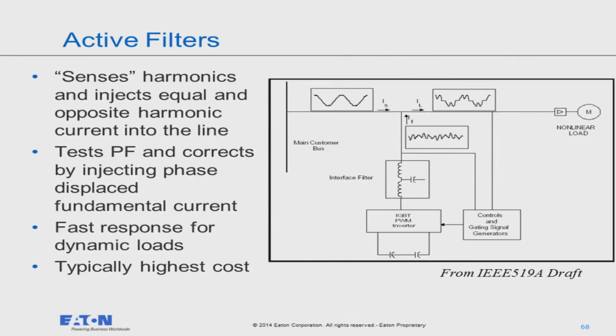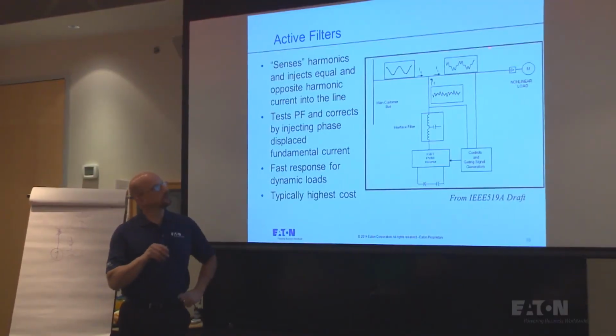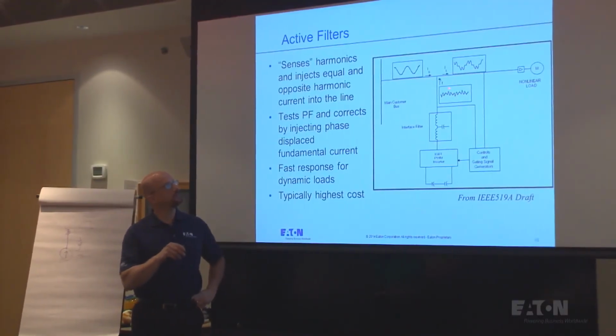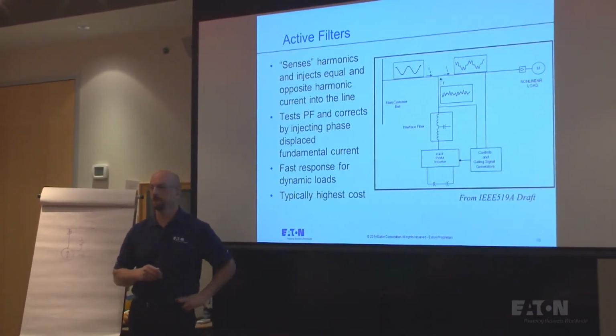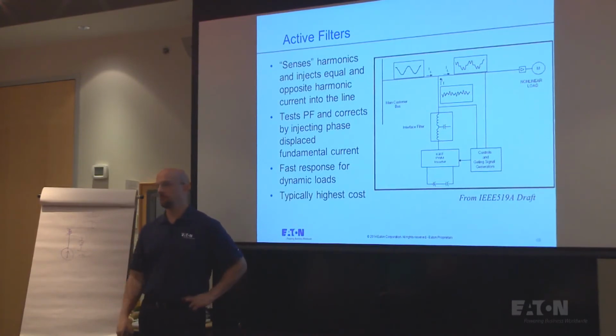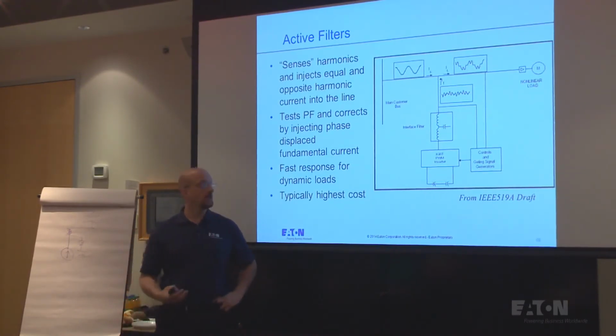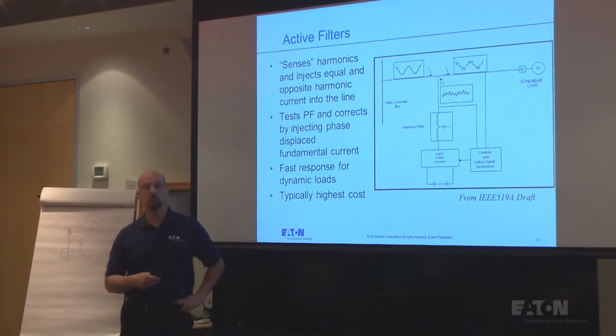Active filters. An active filter would be kind of a system level fix where you have a whole bunch of drives and you don't know what speed they're running and what kind of harmonic output they're generating. But then it'll match up and inject equal and opposite harmonics. So it sees a load that looks like this, it injects this, and these two added together look like that. Does it have to be perfect? No. It just needs to be better than it was, or better than the threshold of pain, so to speak. Okay? And that's actually becoming more and more common.